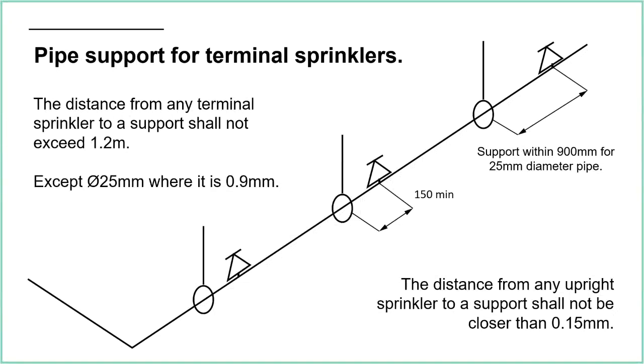A distance from any upright sprinkler to a support shall not be closer than 0.15. I should say 0.15 meters. Sorry, 150 millimeters or 0.15 meters. So what that's getting at is that we don't want a support to be very close to the deflector plate of a sprinkler head, because it may impede the distribution of the water. So just like everything else that you need to watch out for in terms of obstructions of sprinkler heads, we don't want the pipe supports to be one of those obstructions. So yeah, they need to be kept a little bit away from the deflector head.